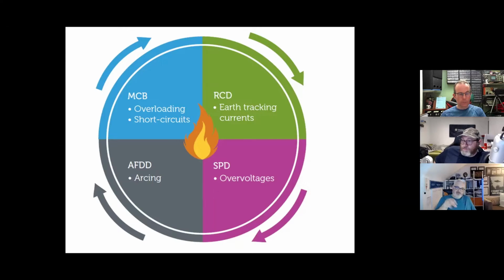And that last part of the circle is the arc fault detection device, which deals with arcing - series connected breaks in cables, and the parallel leaks which an RCD potentially won't pick up. So you have a complete circle of protection there. That's just for those learning. You have to consider all this as you go through your process of elimination to select and erect what's best for your installation.